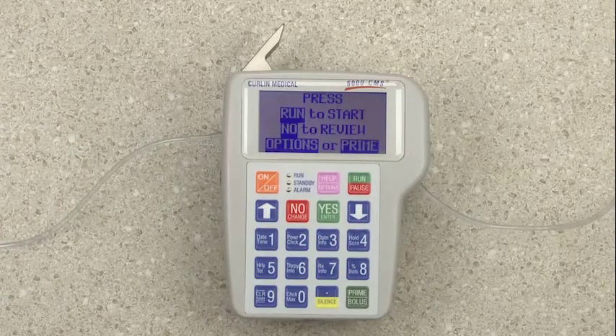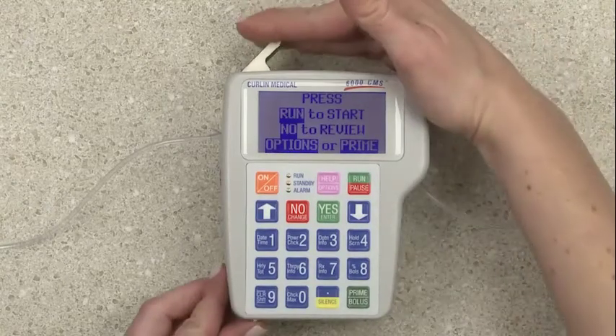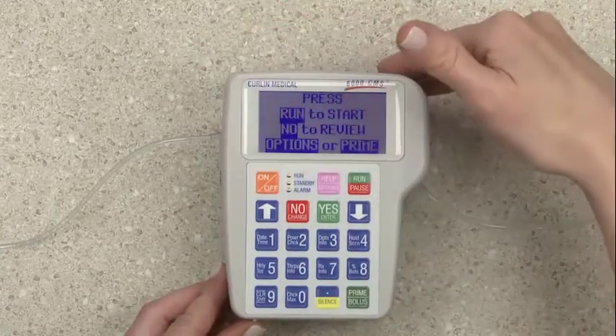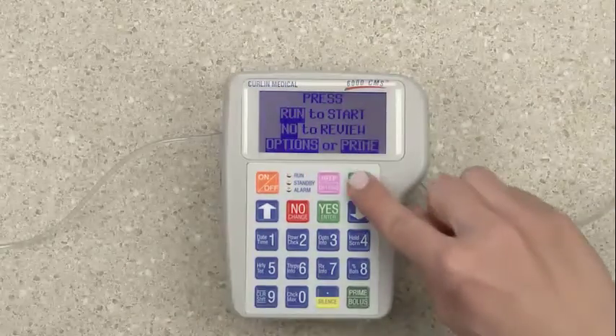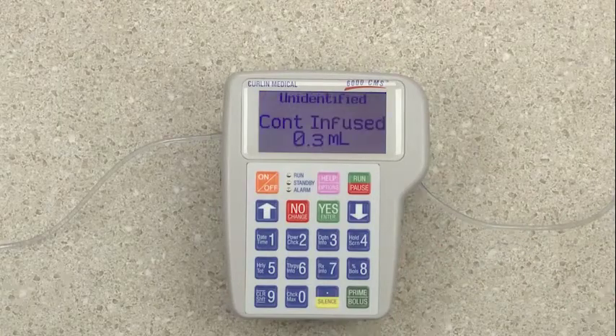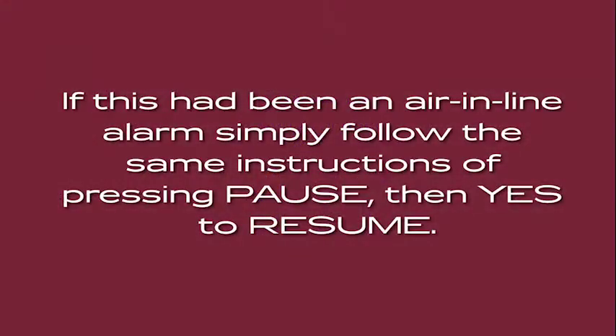From the Run to Start screen, we can troubleshoot the specific alarm. For this alarm, I simply need to close the latch door, and I can press Run to start the infusion. If this had been an air-in-line alarm, simply follow the same instructions of pressing pause, then yes to resume.